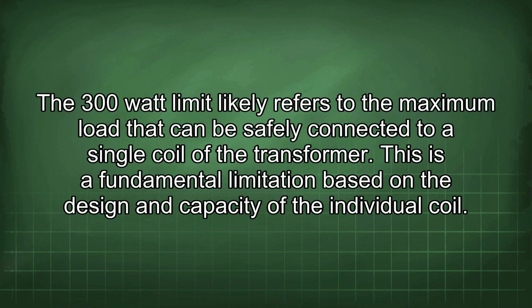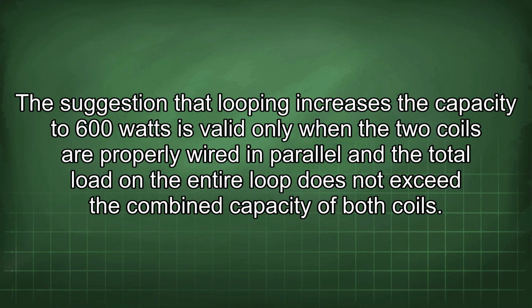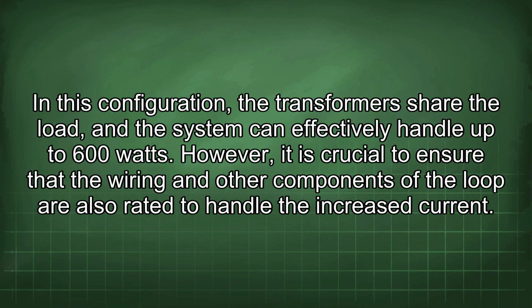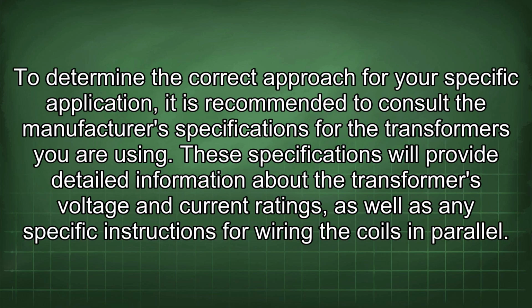The 300 watt limit likely refers to the maximum load that can be safely connected to a single coil of the transformer. This is a fundamental limitation based on the design and capacity of the individual coil. The suggestion that looping increases the capacity to 600 watts is valid only when the two coils are properly wired in parallel and the total load on the entire loop does not exceed the combined capacity of both coils. In this configuration, the transformers share the load, and the system can effectively handle up to 600 watts. However, it is crucial to ensure that the wiring and other components of the loop are also rated to handle the increased current. To determine the correct approach for your specific application, it is recommended to consult the manufacturer's specifications for the transformers you are using.